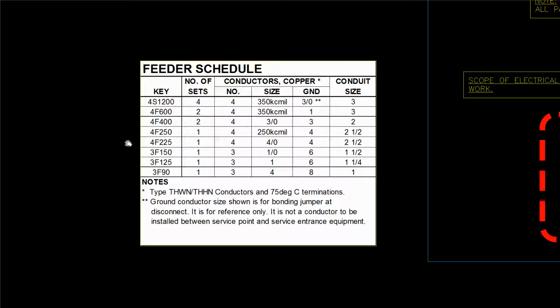so if you have panels of varying degrees, you have 3F, so these are going to be single phase 3 wires, so 3F 125, 3F 150s, and so 125, 150 amp. But then we move up to these 4F, so these are 3-phase 4-wire, and so you've got 4F 225, 250, 400, 600, 1200. What I try to do is rather than just putting this big long schedule on every plan, I want to put this one on there to encapsulate the ones that I'm actually using.